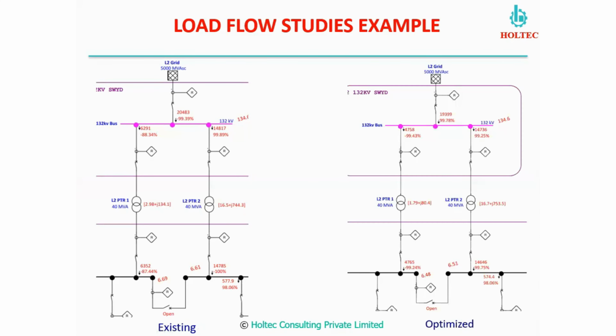Okay, so after optimizing the voltages through the corrective actions, we have been able to maintain 0.99 power factor, which is absolutely perfect as against 0.88 leading. And here you see the power consumption is also reflecting. There is a reduction in the power consumption without doing anything. We have just optimized all the buses voltage and the power factor, and what ultimately we get is the saving in the overall power received from the grid. So this is a classical example where you can say that it is not only by optimizing the power factor, by optimizing the voltages, you will have saving in the power which we receive from any of the source, not only grid.